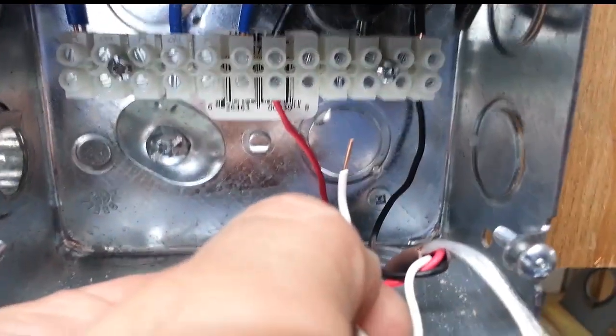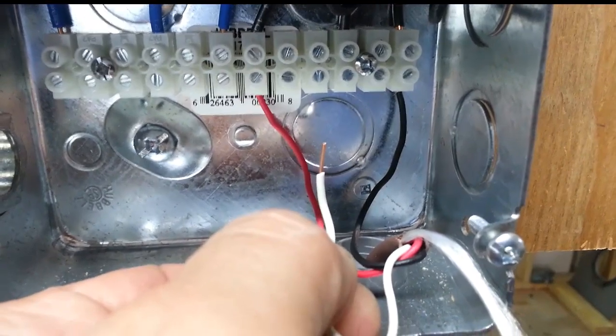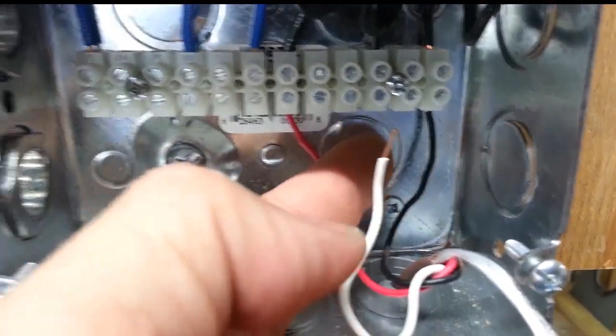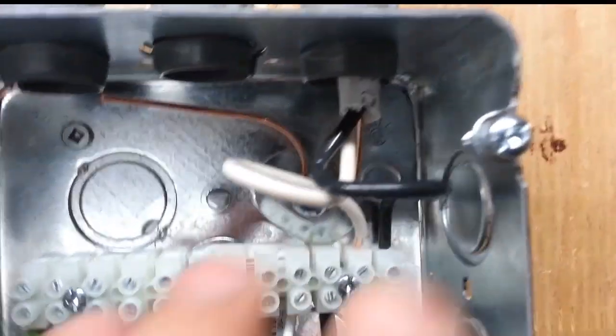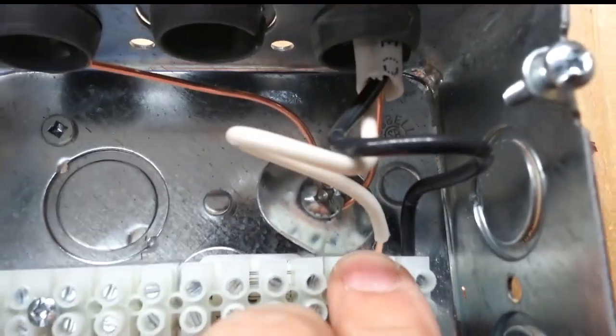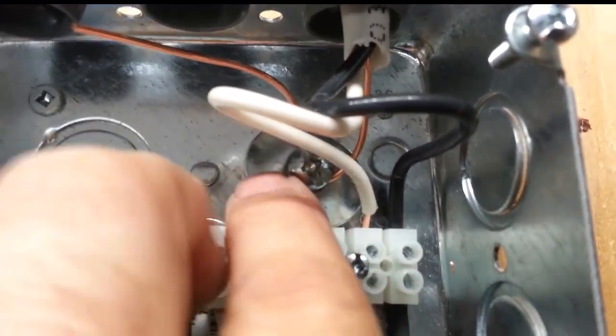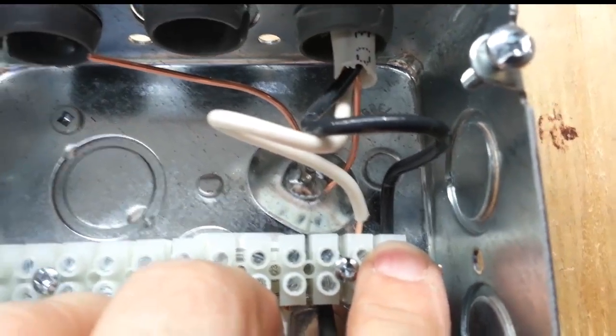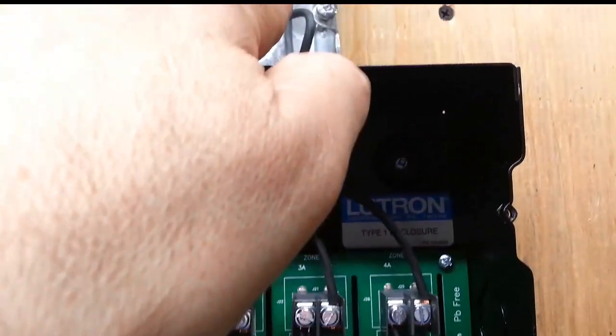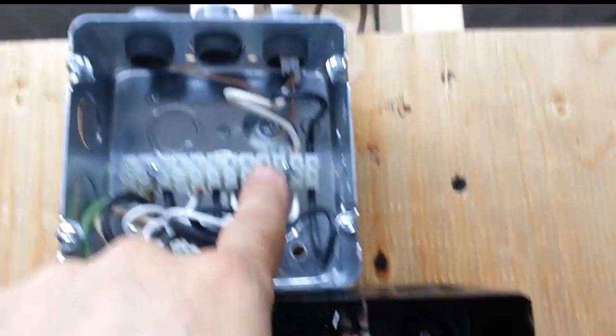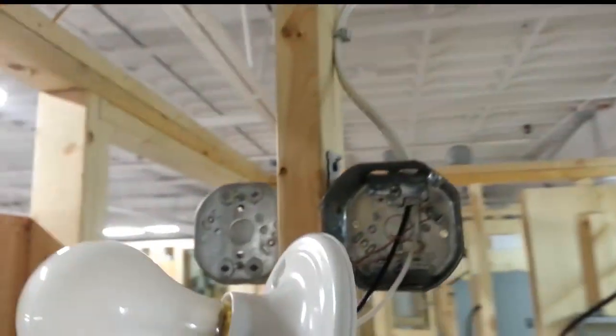You don't have to strip very much. You just need a little bit, a little amount there, a quarter inch, any longer. And then you'll have the wire sticking out, and there's a possibility of shorting out to the back of the box. That same rule applies to when you're hooking up your actual 120 volts. So this wire is going back to the actual light. As you can see, the black wire has been stripped correctly. The white is a little long, and you don't want that because in case it short out the back of the box, you'll have a dead short. So that 120 volt that is fed from the panel comes up. When it's turned on, it goes to the black wire. It also gives it neutral, and it will go to your light that has been hooked up.